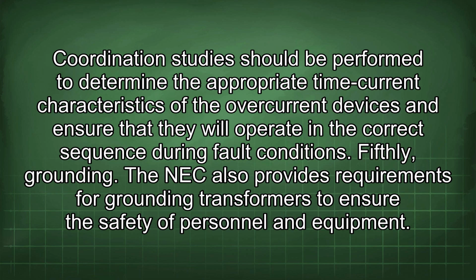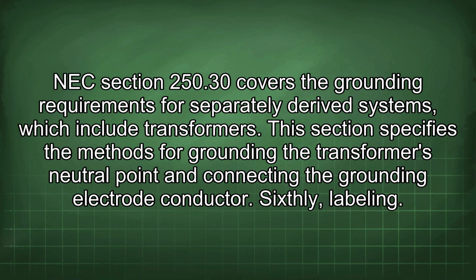Fifthly, grounding. The NEC also provides requirements for grounding transformers to ensure the safety of personnel and equipment. NEC Section 250.30 covers the grounding requirements for separately derived systems, which include transformers. This section specifies the methods for grounding the transformer's neutral point and connecting the grounding electrode conductor.